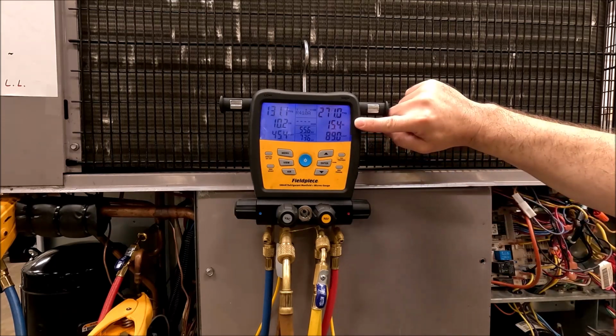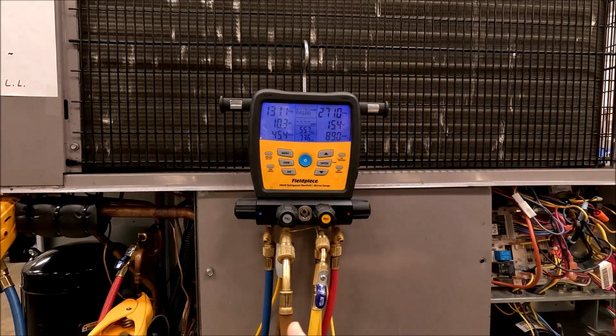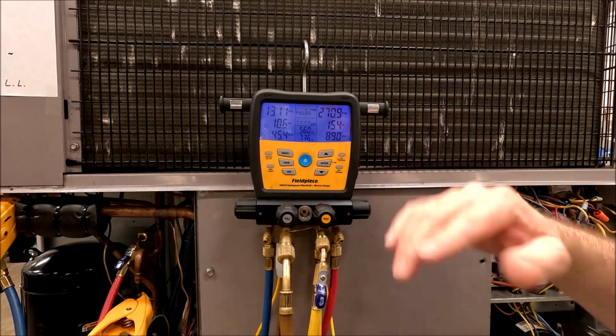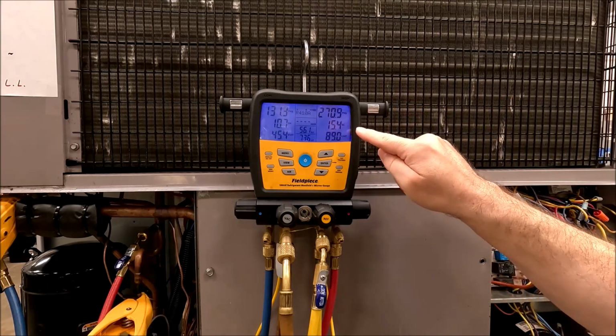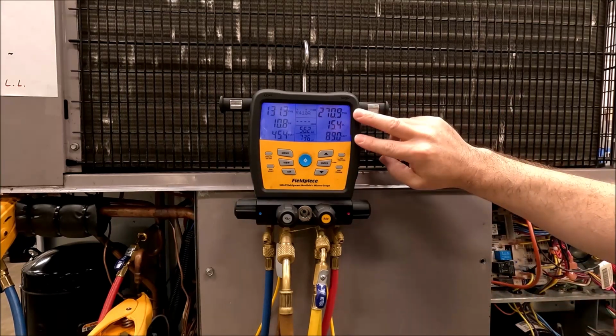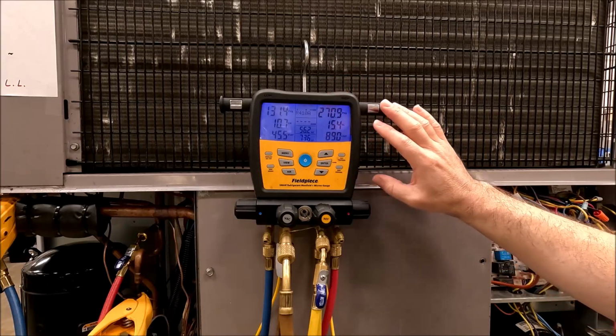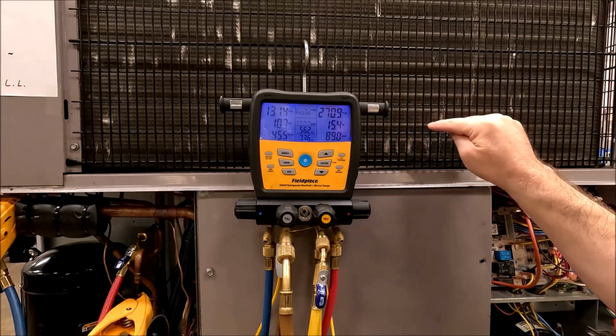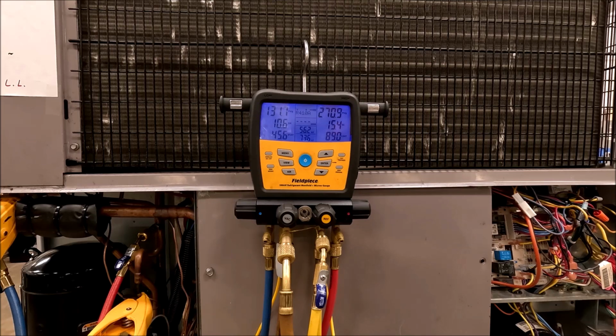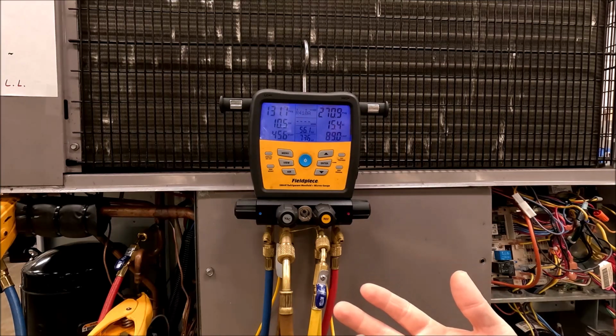Subcooling values here in the middle. It knows the liquid line has to be colder. If it's not, if you hook it on the discharge line, which I'll show you in a second, that's the point of pulling this over here. It's got like a spreadsheet built in, right? It knows where to put that number you tell it on that pipe clamp. If you put it in the wrong spot, it doesn't compute right.